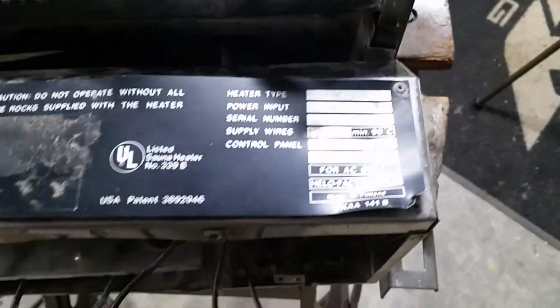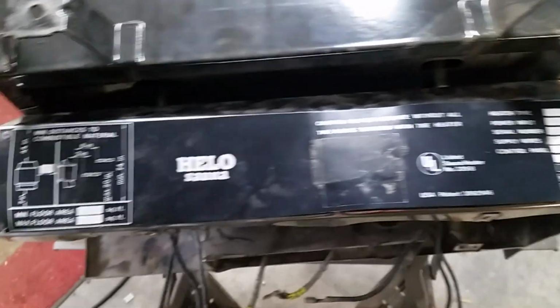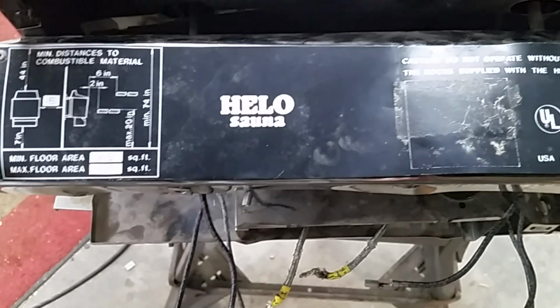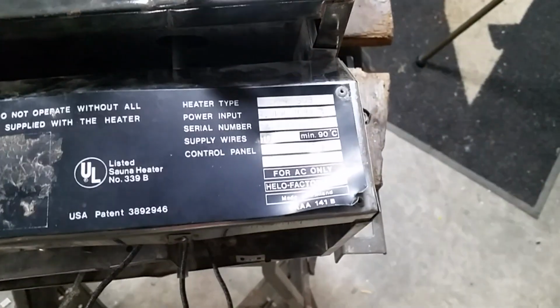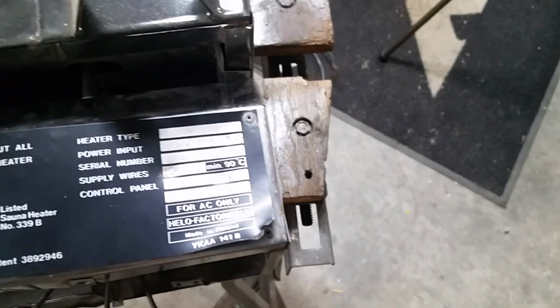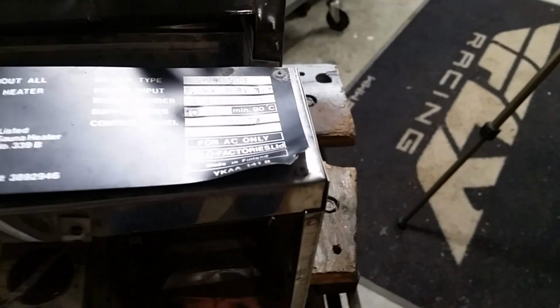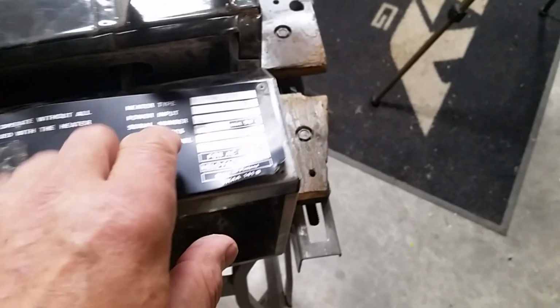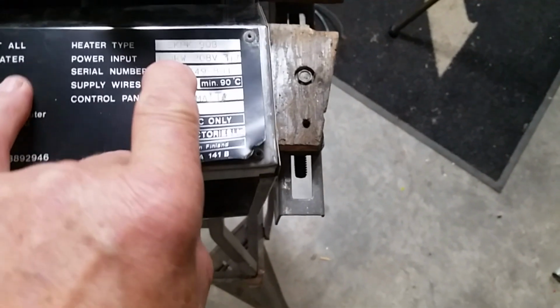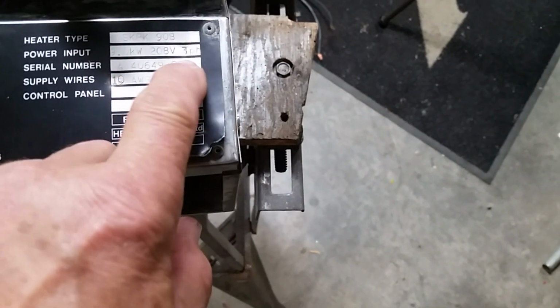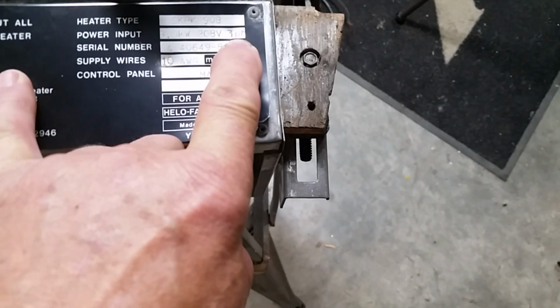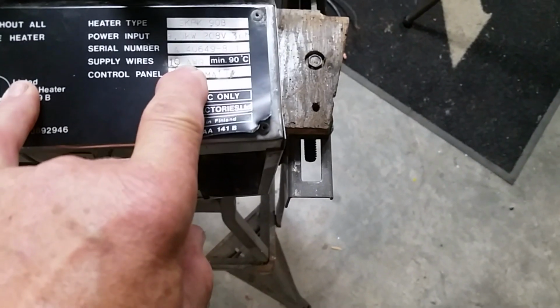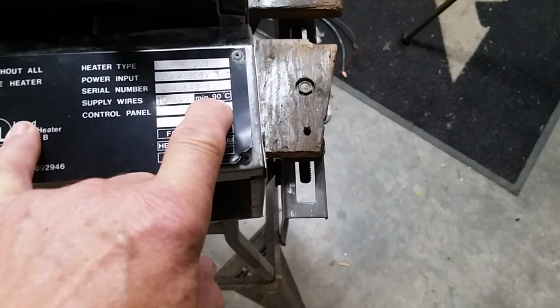This is the basis of my load tester. It is the heating elements from a sauna, a Helo sauna. However, it's not really made for the house. You can't see it very well, actually can't see it at all because it's too fuzzy, but this is a 9 kilowatt, 208 volt, 3-phase unit, and it uses 10 gauge wires with a minimum rating of 90 degrees centigrade.